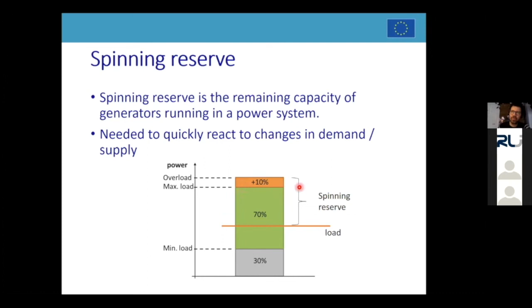And I know that usually you run your diesel systems so that you have quite a good spinning reserve, so if the load increases, you would switch on a second generation unit to provide always enough spinning reserve. And batteries could also provide this. So a charged battery can react even quicker than a diesel generator. So if you have batteries in your system, you can reduce the amount of conventional spinning reserve or even switch the generators off.